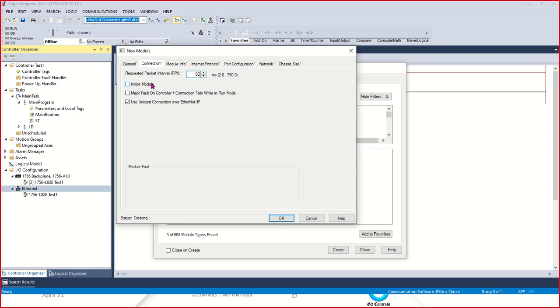It will be there, but it will not work anymore, because you inhibited the module. If you have some error or trouble in the working of one equipment module, and you don't want that equipment module to run for more time and create trouble for other lines, you can inhibit that module and run your line continuously.